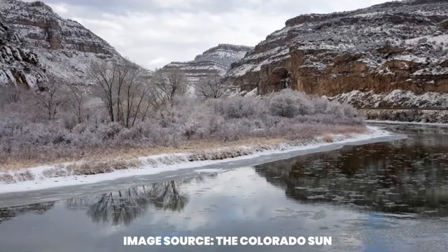The other thing we do, sometimes you have to go old school. Rather than just doing flow monitoring, we also start observing the color of the water will change. When you have a snow melt, that snow melt water should not be in the collection system.